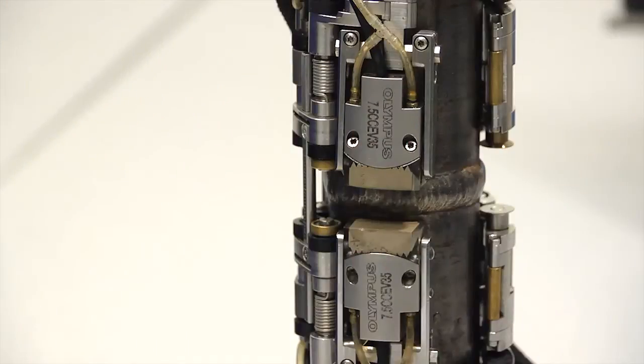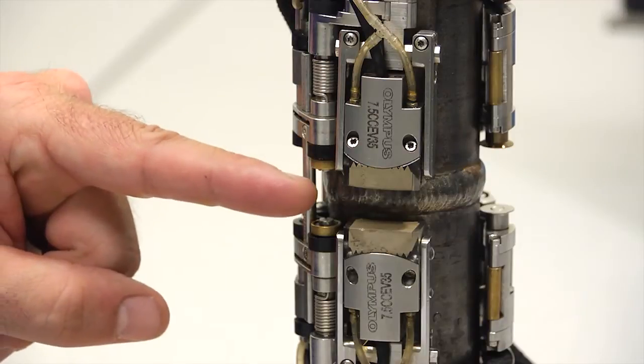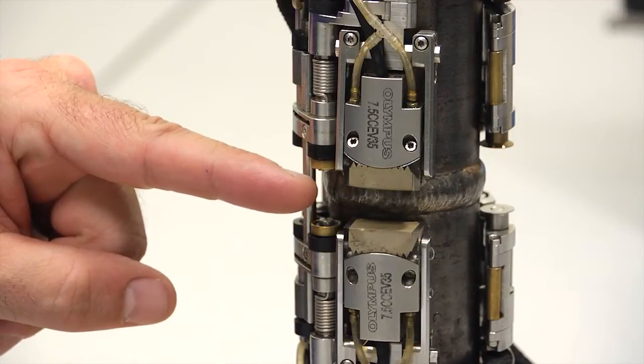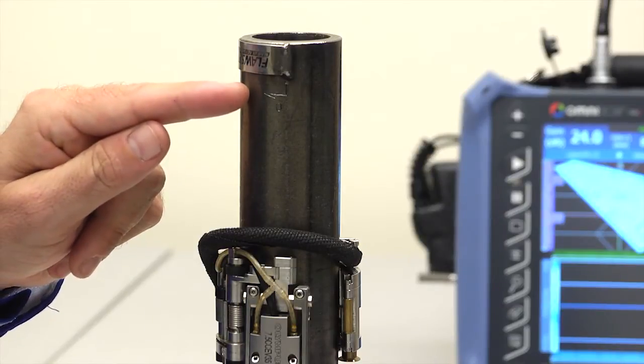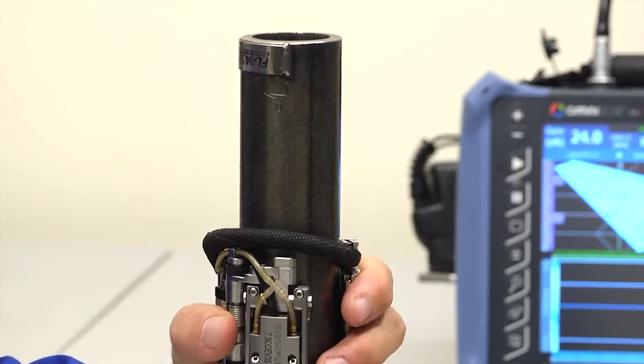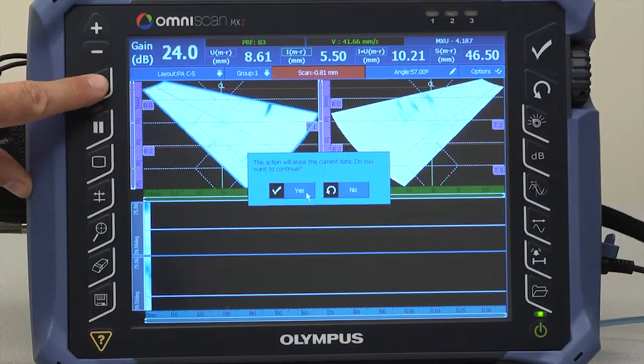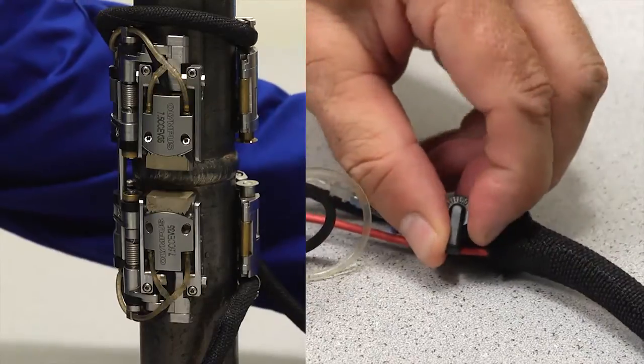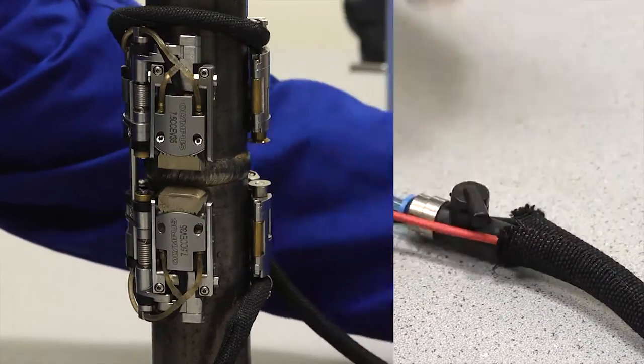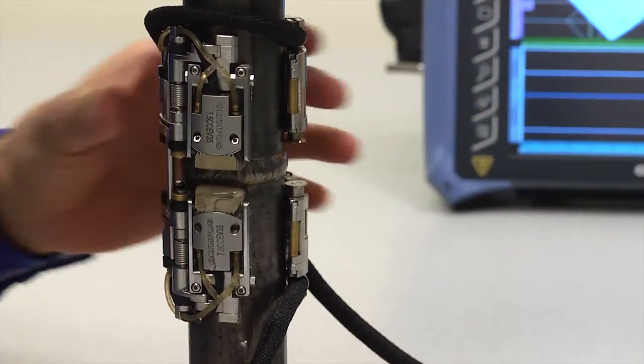The probes are secured in the scanner at the predetermined position relative to the weld centerline. The scanner is placed on the pipe at the inspection start position. Select start inspection on the OmniScan, start the water supply, and move the scanner around the pipe smoothly.